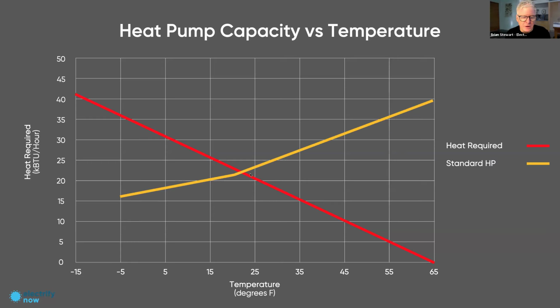There will be what's called a crossover temperature, which is the maximum cold temperature at which the heat pump is still able to deliver the required heat to keep your home at 70 degrees. In this generic chart, for explanation purposes, that crossover temperature looks like around 20 or a little over 20 degrees. That means if it gets below 20 degrees, you're going to need backup heat, because your heat pump won't be able to maintain the load.